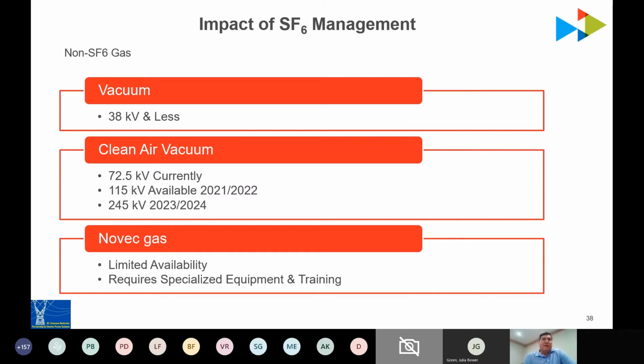Maintenance is going to be a little different with clean air. It's going to be a lot easier. The O&M we'll save is that we don't have to have all this process equipment capturing the gas, all the testing equipment we require today, and the compliance piece is going to get easier with clean air vacuum as well. So we looked at how we'll be able to save some money over the life of the asset that we're spending with the SF6 version of the dead tank breaker versus its clean air technology counterpart.